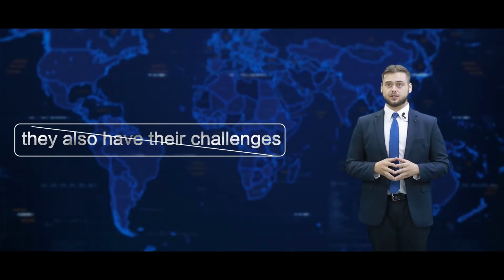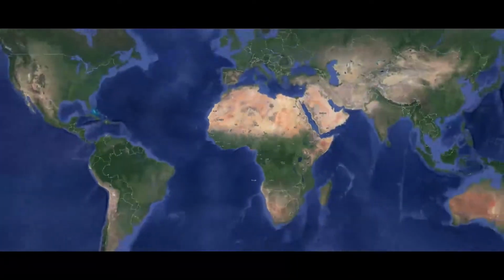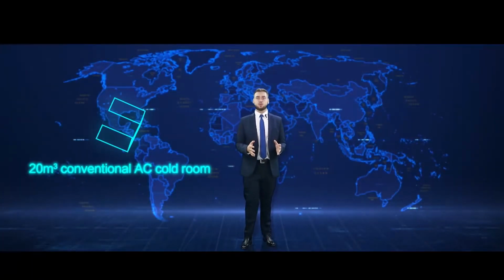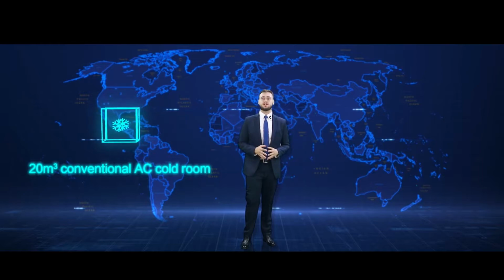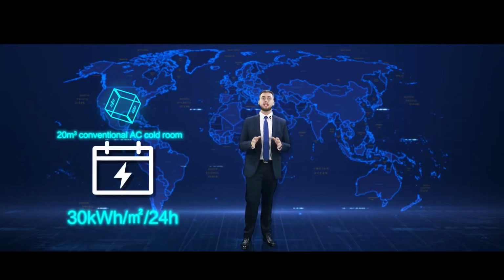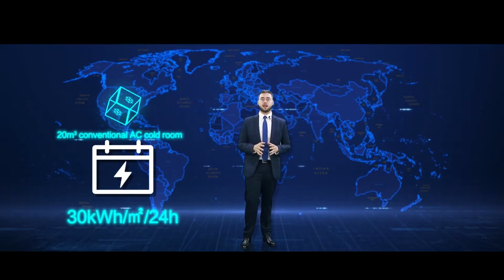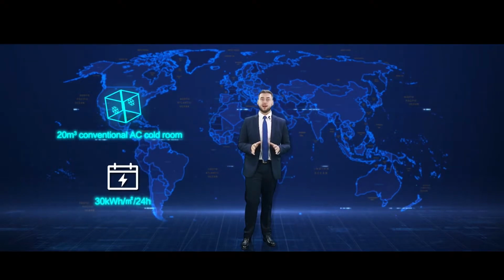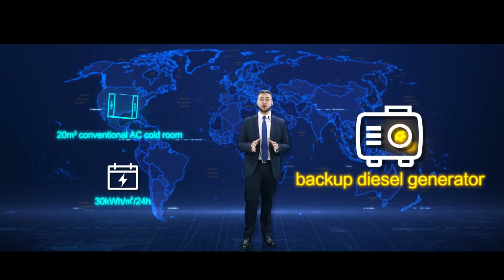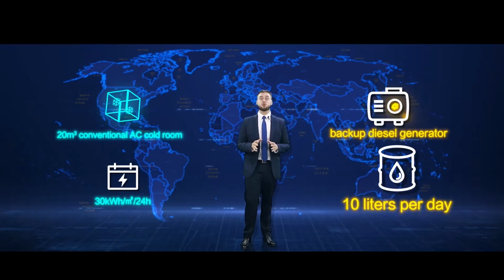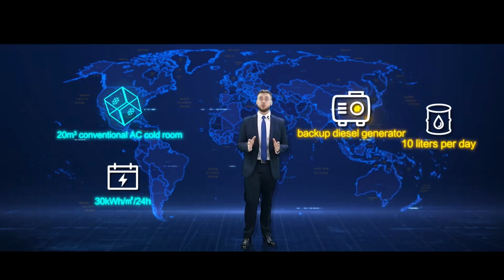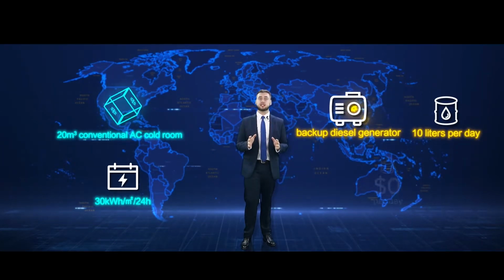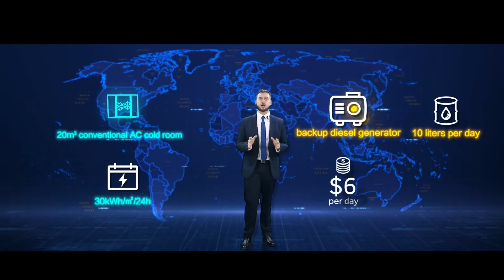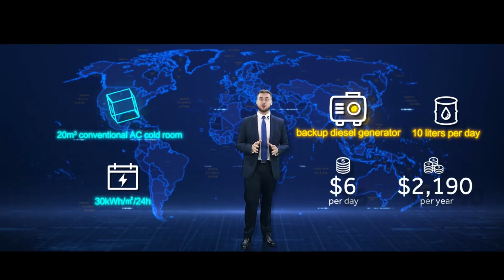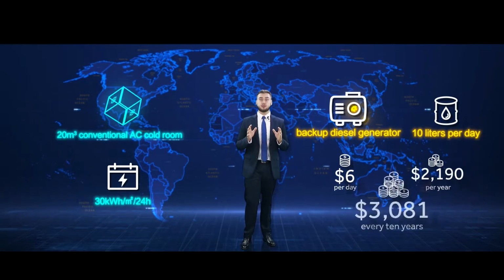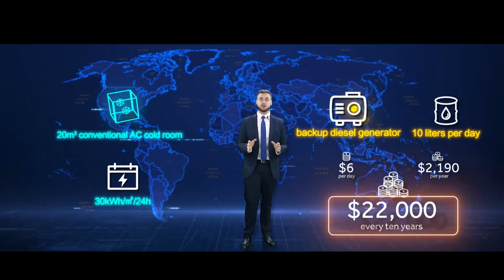For example, the daily power consumption of a 20 cubic meters conventional AC drive cold room used in Nigeria can reach up to 30 kilowatt hours per square meter. If the power is supplied by a diesel generator, then the fuel consumption will be 10 liters per day, which means the cost of fuel will be at least $6 per day, $2,190 per year, and $22,000 every 10 years.